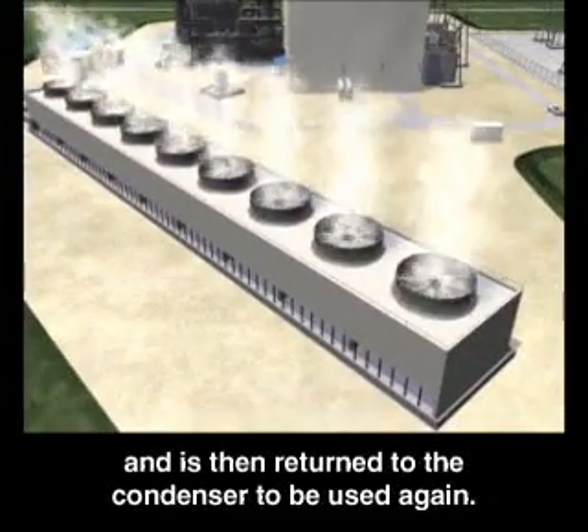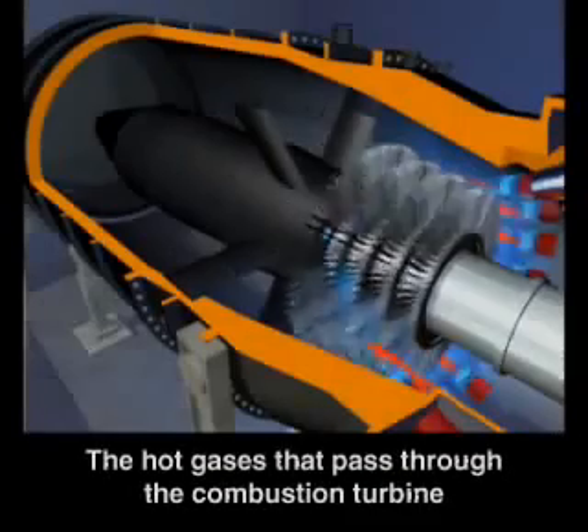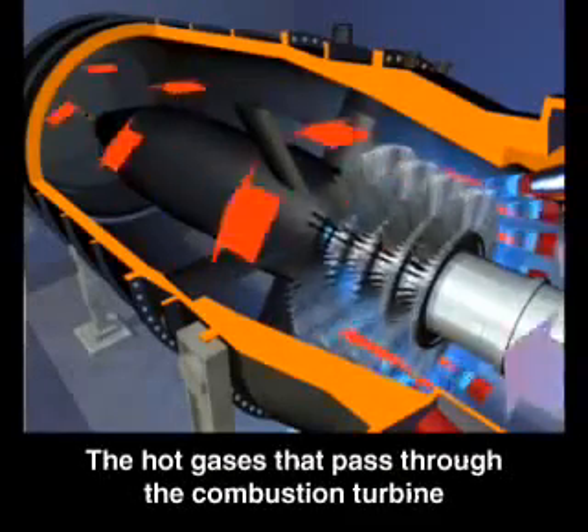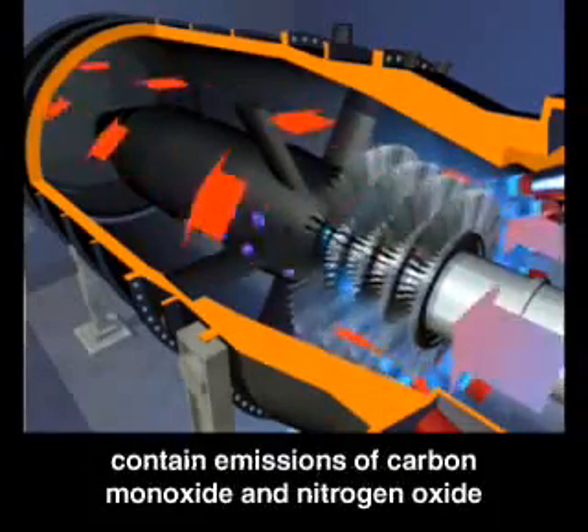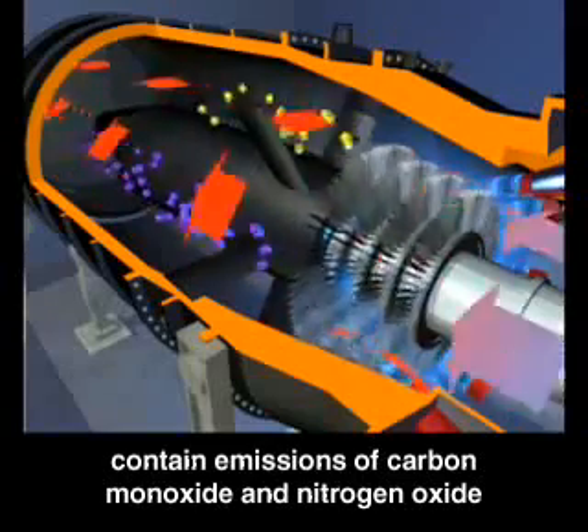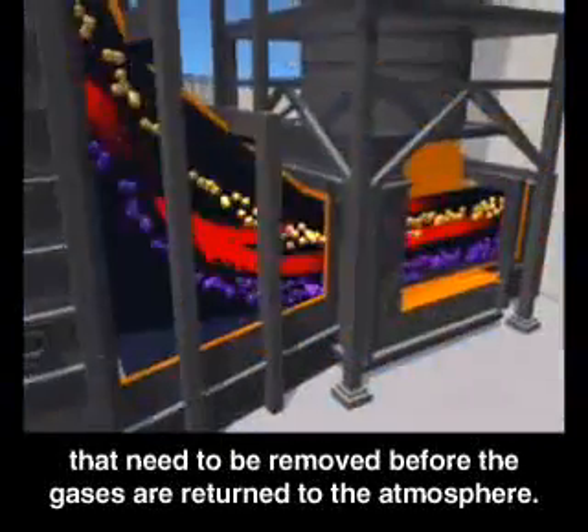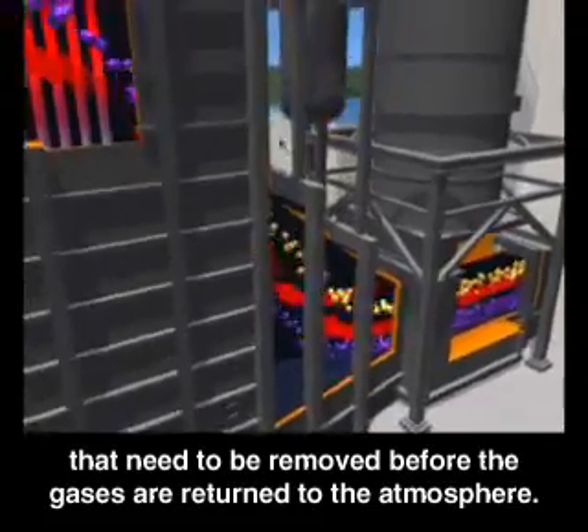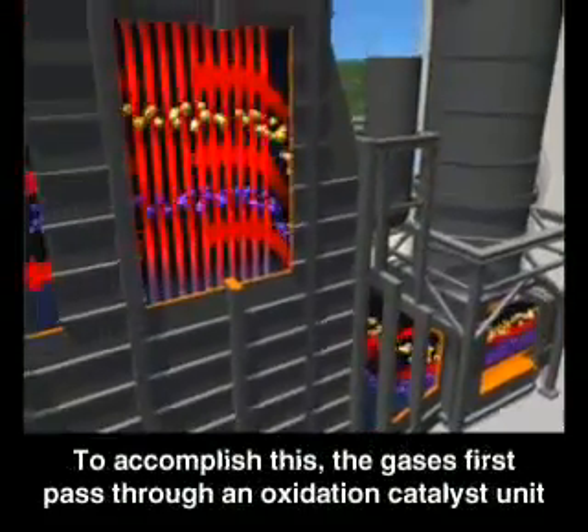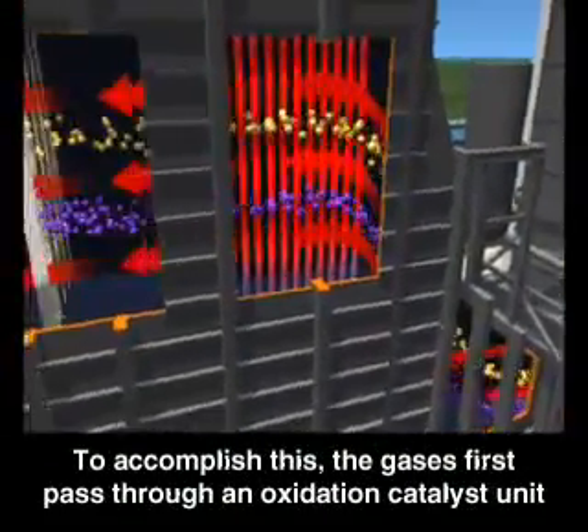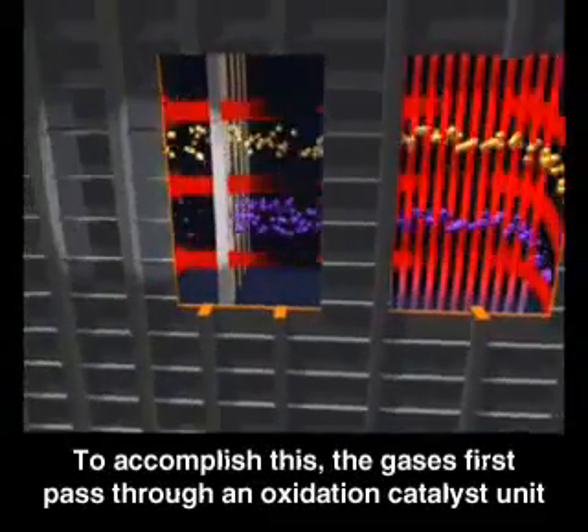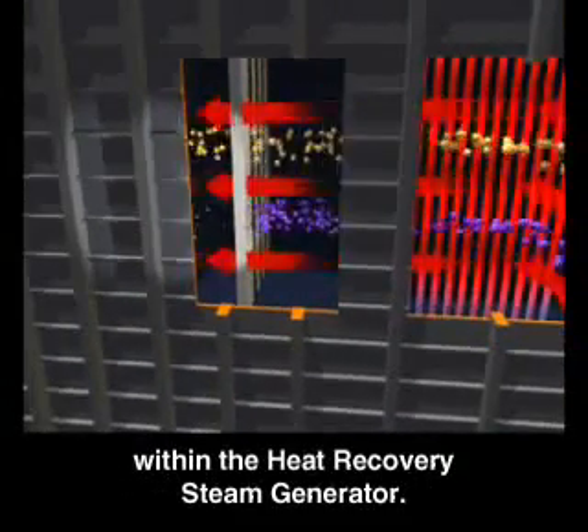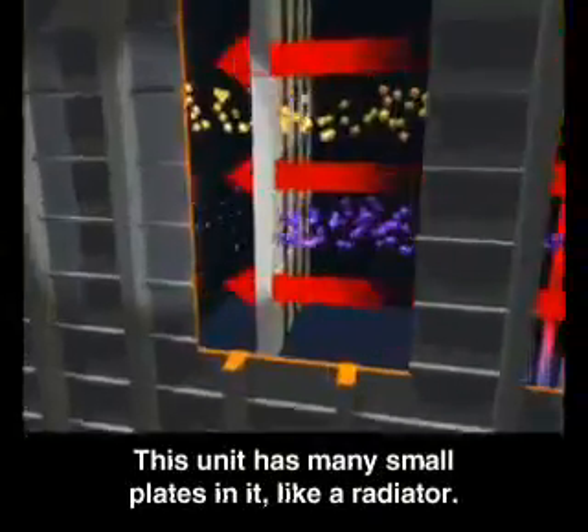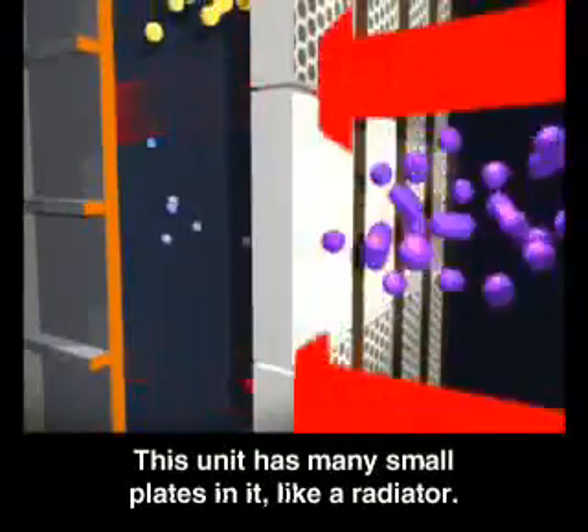The hot gases that pass through the combustion turbine contain emissions of carbon monoxide and nitrogen oxide that need to be removed before the gases are returned to the atmosphere. To accomplish this, the gases first pass through an oxidation catalyst unit within the heat recovery steam generator. This unit has many small plates in it, like a radiator.